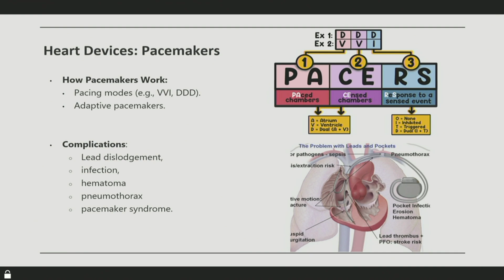Pacemakers are not without complications, of course. It is a foreign body that's introduced, and as with any foreign body, there are some complications. One of them is lead dislodgement, especially after you've implanted, if there is ineffective pacing or inappropriate sensing. Sometimes these leads need to be repositioned and brought back to the EP lab. Infections are also a concern, especially in the pocket of the pacemaker. If that is not kept sterile, or if a patient comes in with bacteremia and sepsis, those leads are foreign bodies. They can be infected, and at that time, they may even need removal of the pacemaker, or at least exchange of those leads.